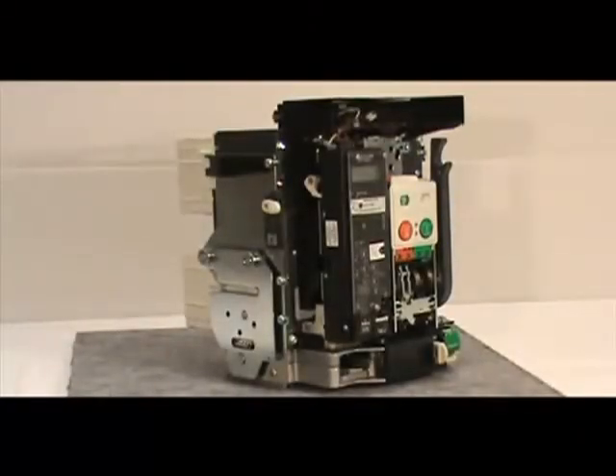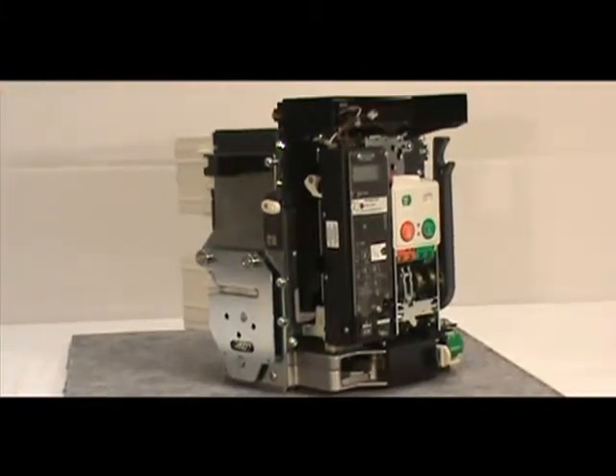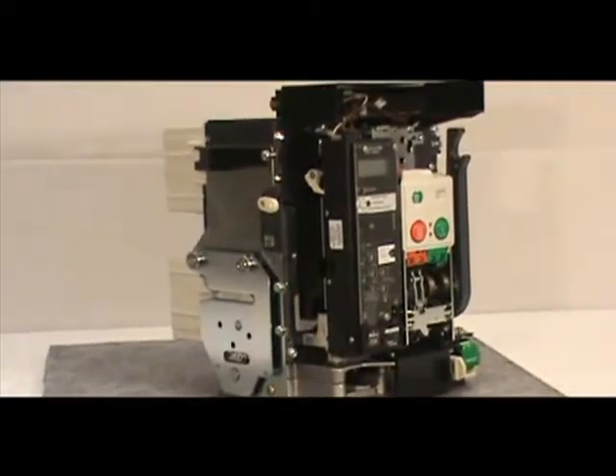Next, locate the left accessory tray. It is behind the trip unit. Put a finger on each end and slide the tray to the left. A minimum of 2 inches of side clearance is needed for tray removal.